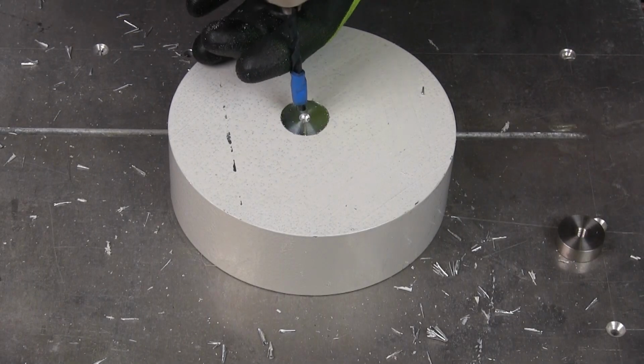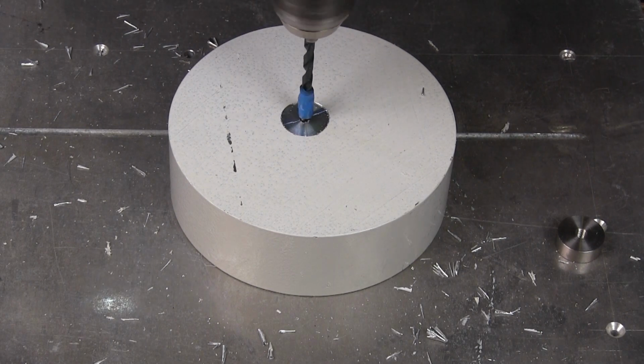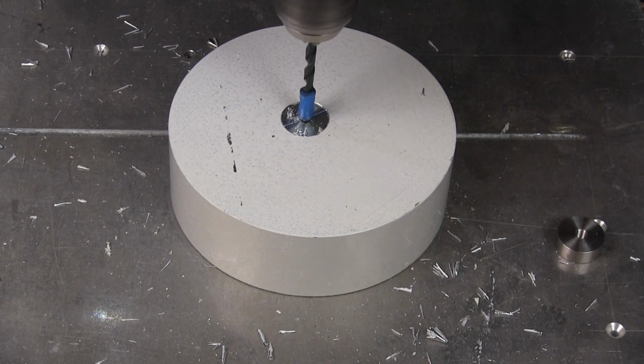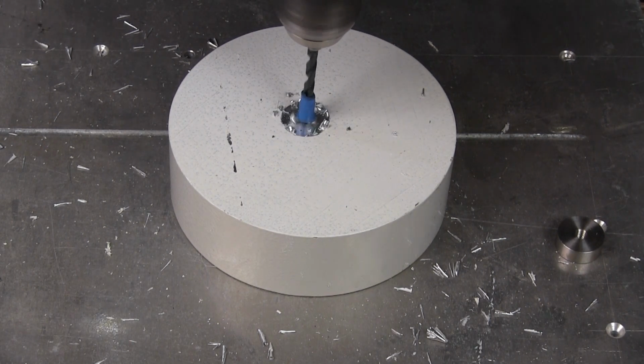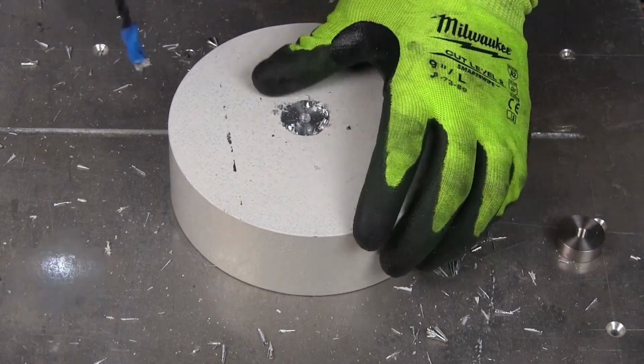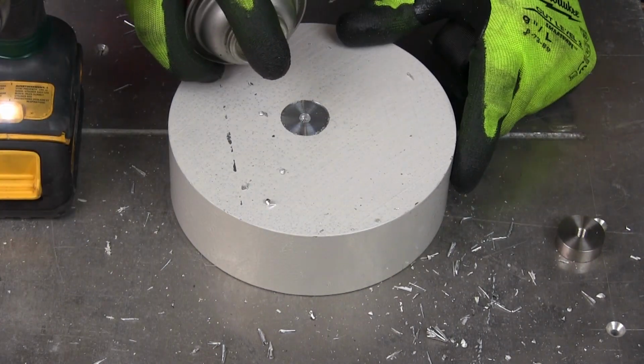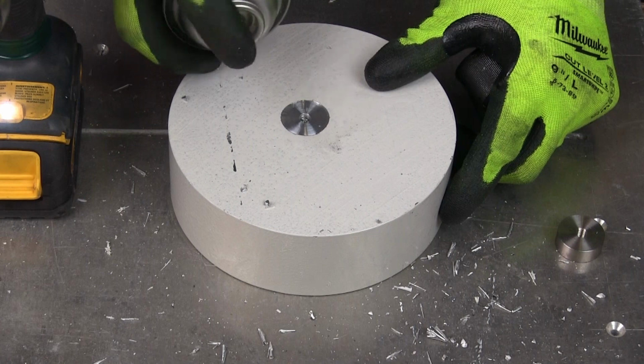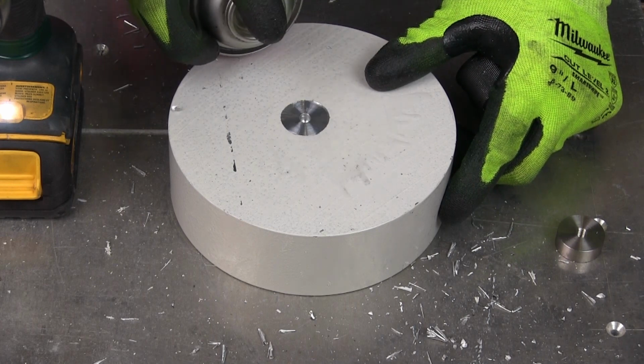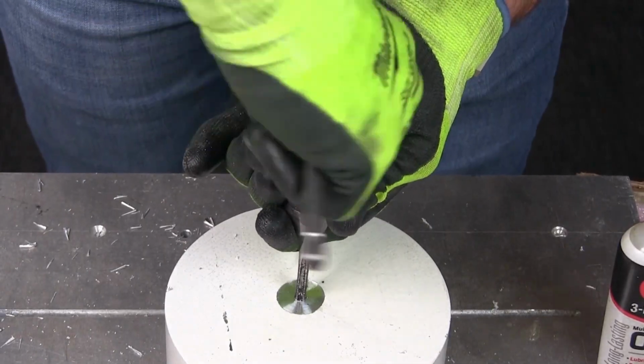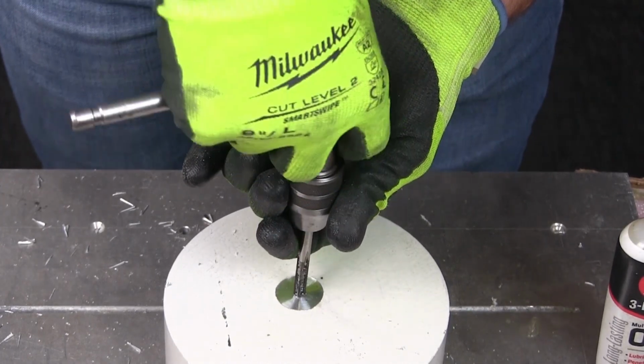The depth of the pilot hole should be at least 1/4 inch, or 6 to 7 millimeters. Ideally, our spot face diameter is at least 1.1 times the diameter of the accelerometer's mounting surface. Tap with the appropriate thread, in this case 1/4-28.